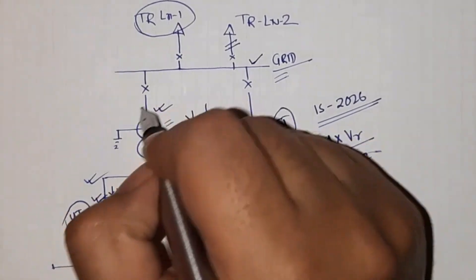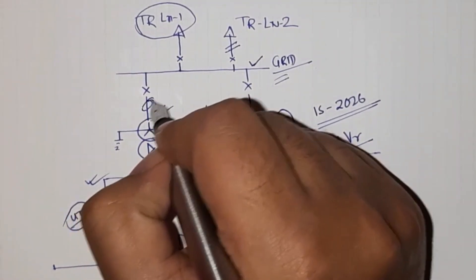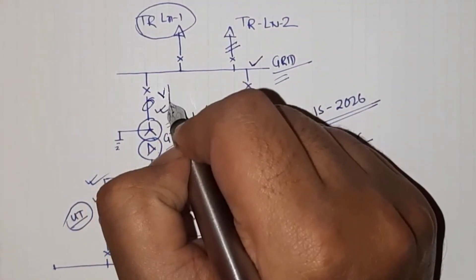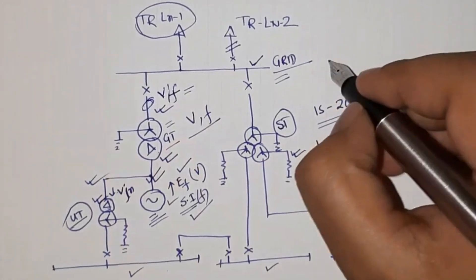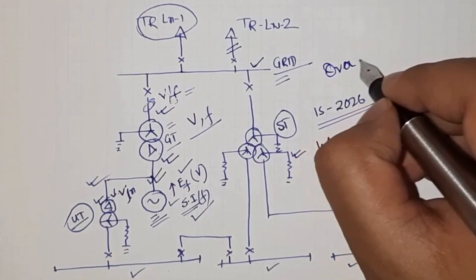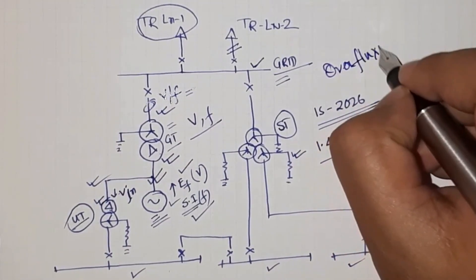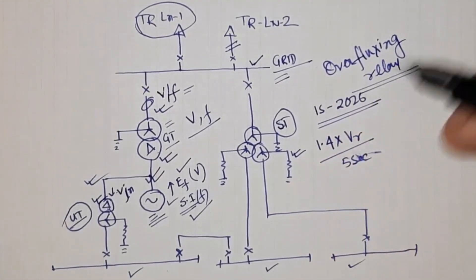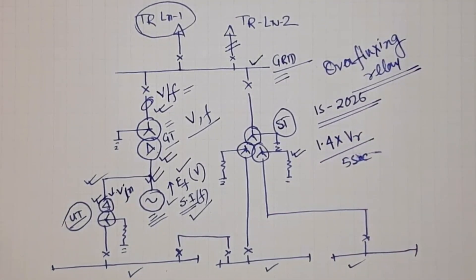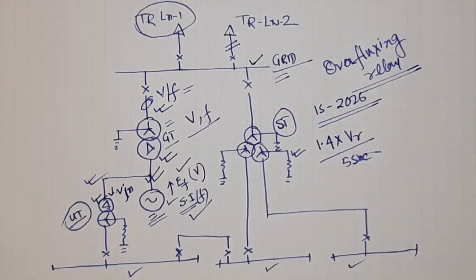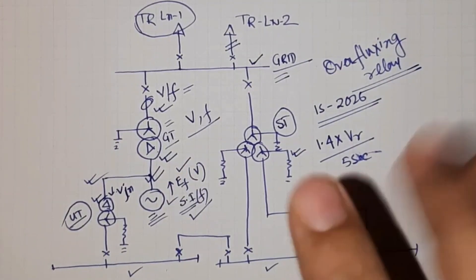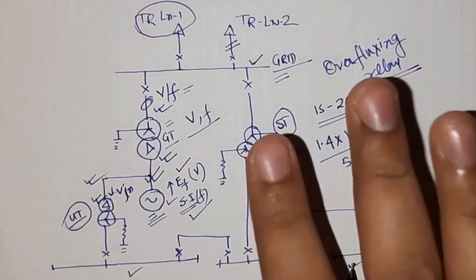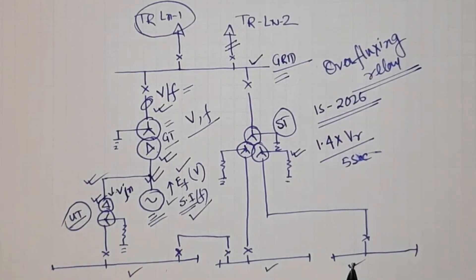That is also the reason why the generator transformer includes a V/f relay, also called an over-fluxing relay. The over-fluxing relay monitors the V/f ratio to detect over-fluxing occurring in the transformer and isolates the system from the main supply when required. This is the main difference between a transformer connected with the generator and a station transformer.